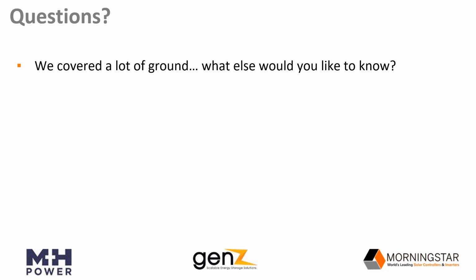All righty. And I think Brad answered a similar question to this before. Question was, how many Morningstar regulators can you run on a system in parallel? You want to take that one, Brad, or just refer them to it? The parallel option. We don't have a fixed number. It's kind of like what Albert said. It really starts to become limited by the power bus and just making it work, because they're not communicating. There's not any kind of network ID or communication setting that's a limit. It's more what's practical in terms of current and the DC power bus in terms of amps.